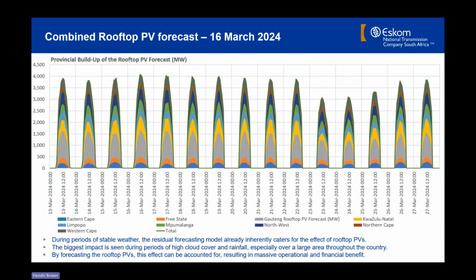So even though you've got PV production and then it gets supplemented by your battery energy supply, because it's still being supplied, it means that that is a portion that we do not have to supply. So since that is the case, and it's a general practice, and I think most of the installations come with a storage capability, it's already inherently included in your demand component, or let's alternatively call it the demand component that we do not need to supply.